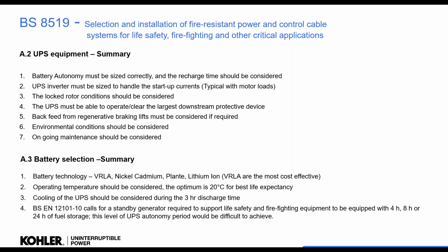The UPS must be able to handle all the startup currents, we'll look at that. Locked rotor currents for motors. Being able to operate the downstream protective device is very important, and this is hopefully very familiar in a healthcare environment, when we do use UPSs for those medical critical areas. If we're feeding lifts, we might have regen lifts, we have to consider it. And we should consider where the UPS is installed and operated environmentally. And this, along with the maintenance, is something that we have seen over the last few years. People are installing UPSs in bad environments and not maintaining them. So the regulations are catching up to help us with this.